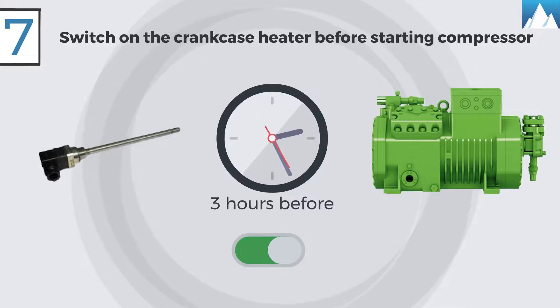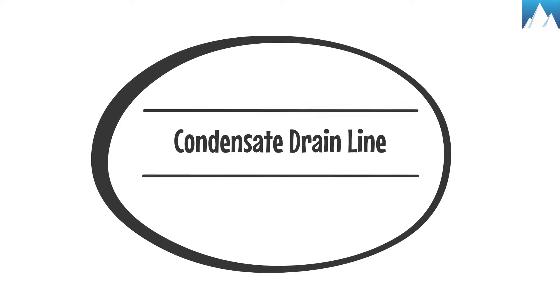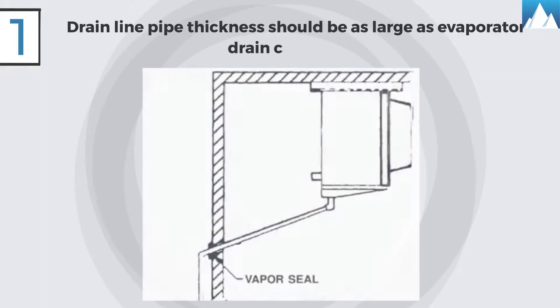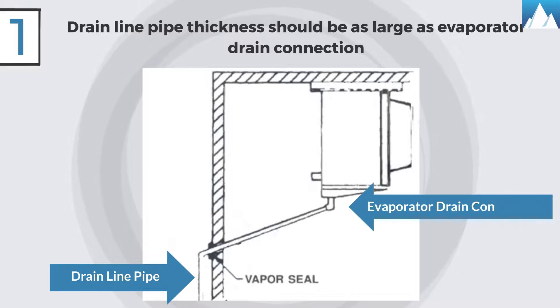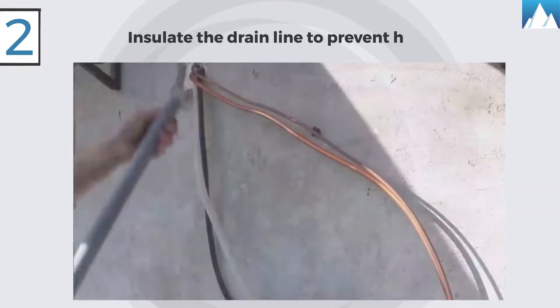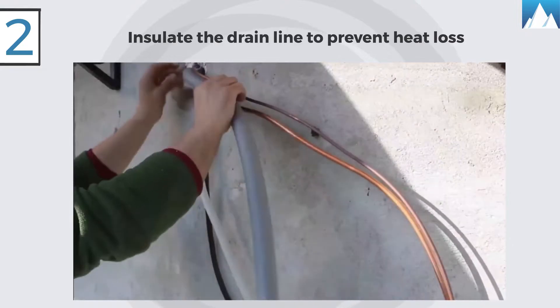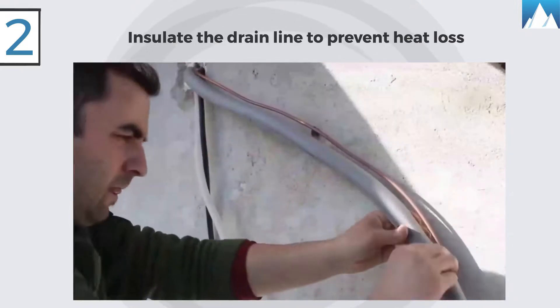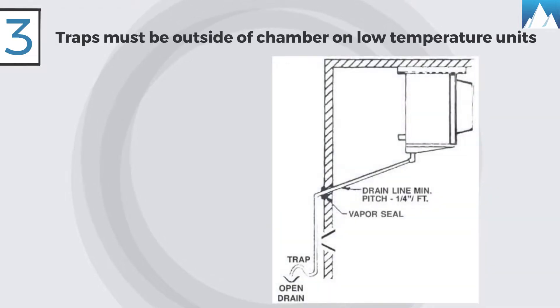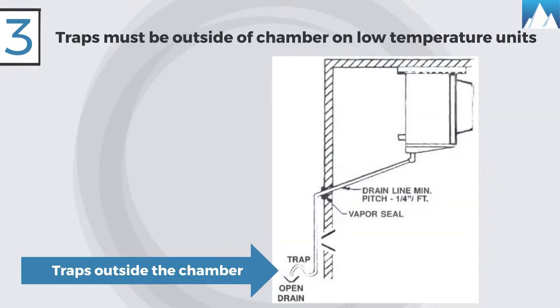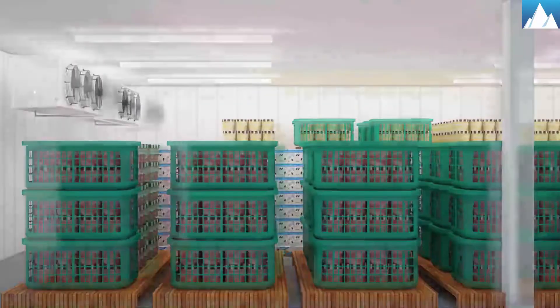Seven, switch on the crankcase heater three hours before starting the compressor when you are starting the unit for the first time. Condensate drain line: One, thickness of drain line pipe should be at least as large as the evaporator drain connection. Two, it is recommended that the drain line be insulated to prevent heat loss. Three, traps on low temperature units must be outside of refrigerated enclosures.